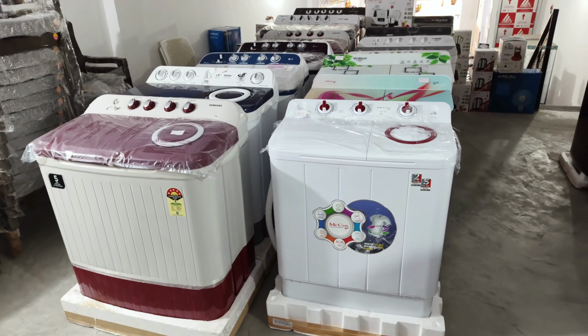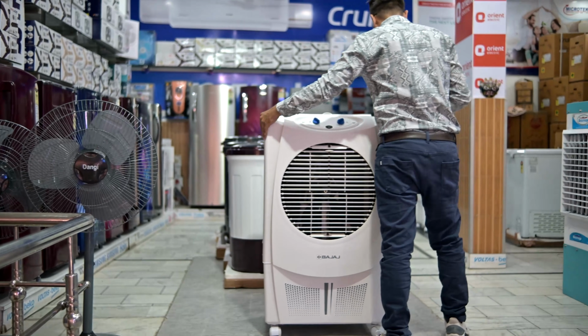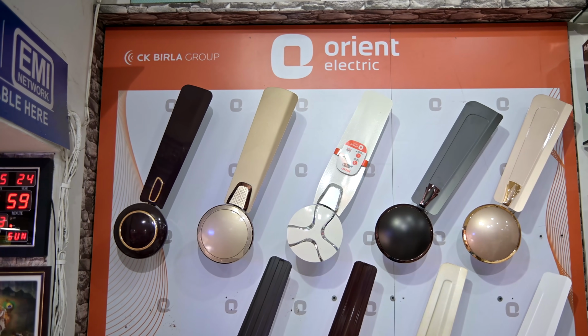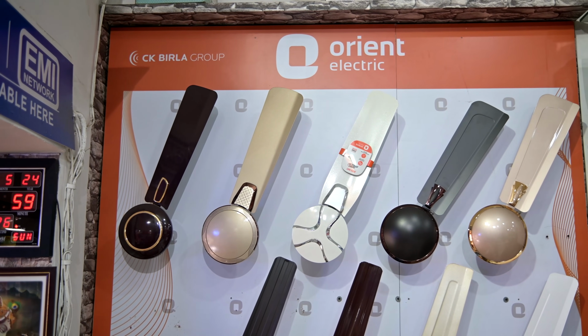This is because from 1 kilowatt of solar panels, you usually get around 4 to 5 units of electricity. And inside the battery, you can store about 1 unit. So roughly, you have around 5 to 6 units available with which a 500 watt load can run for around 10 hours. Now, within this 500 watt load, you can run any combination of appliances. For example, you may run a washing machine that consumes the full 500 watts, or you may run a large cooler that takes about 500 watts of power, or you may run 3 to 4 fans along with lights where the total load becomes 500 watts. The important point is that your total load should be within 500 watts. Then you can run it on 1 kilowatt of panels for around 7 to 8 hours, and with the battery, it can run for close to 10 hours.